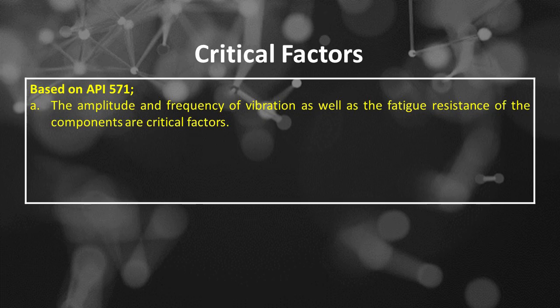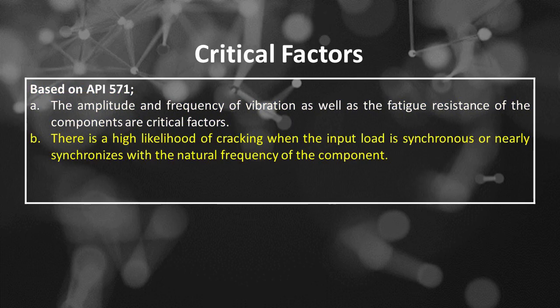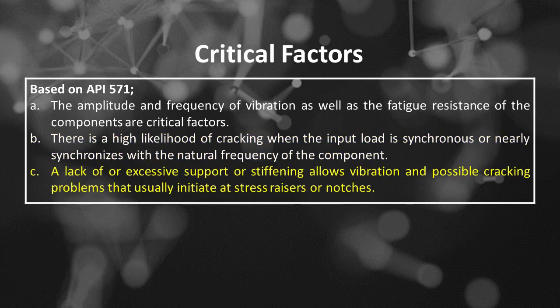Vibration-induced fatigue critical factors based on API 571. The first is the amplitude and frequency of vibration as well as the fatigue resistance of the components are critical factors. The second is there is a high likelihood of cracking when the input load is synchronous or nearly synchronous with the natural frequency of the component. The third is a lack of or excessive support or stiffening allows vibration and possible cracking problems that usually initiate at stress risers or notches.